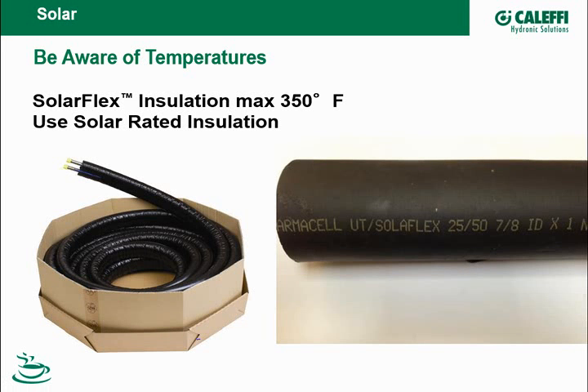It's probably a good quality insulation if it just smells like foam, like the typical foam you'd see at a box store type of insulation. You don't want to use that on solar because you're going to end up with just a big gooey gob dripping off your pipe someday. So you can get the pre-insulated tube from us, or if you have to do some short sections of straight piping, I would encourage you to look for a solar-rated insulation on the solar installation.